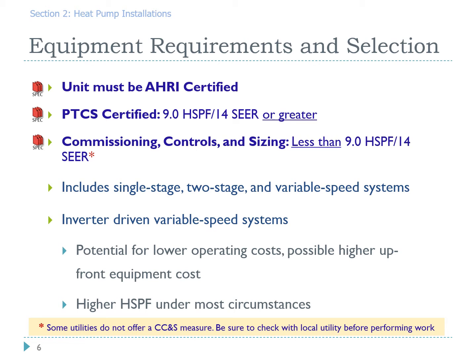Let's dive into the specifications. The first one is equipment requirements and selection. To the left side of the screen, you'll see a little red file folder. That's going to indicate that this is a requirement and a specification. So the units must be AHRI certified. A PTCS certified system is going to have a 9.0 HSPF, 14 SEER or greater rating.